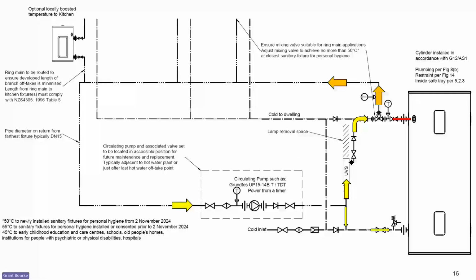You'll see also there the note that these UV sterilizers, we'll have a look at one in a slide a little bit further on, have a bulb the length of the unit, and that we leave space in order to get the lamp out of that UV sterilizer. I've seen some really creative arrangements of pipes in order to allow people to get those bulbs out. So just have a bit of a think when you're laying out your pipe work. Make sure you've got the UV sterilizer there and make sure you've left yourself space to get that lamp out of that unit.